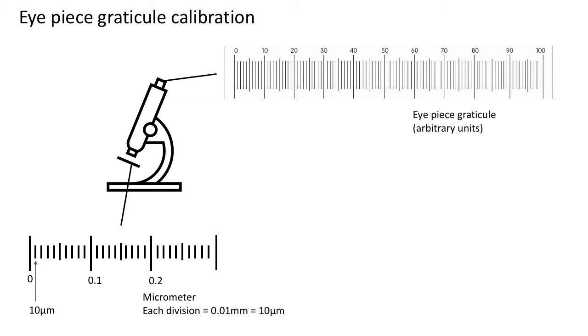The first thing you have to do if you want to use the eyepiece graticule is to calibrate it against the micrometer. Once you've done that, you can move around your sample anywhere and you will always be able to position that sample on the eyepiece graticule and take a measurement because you will know what each of those divisions is equal to.